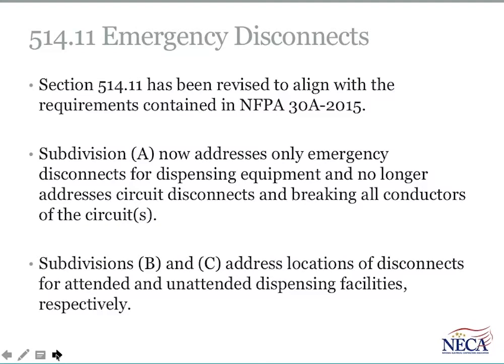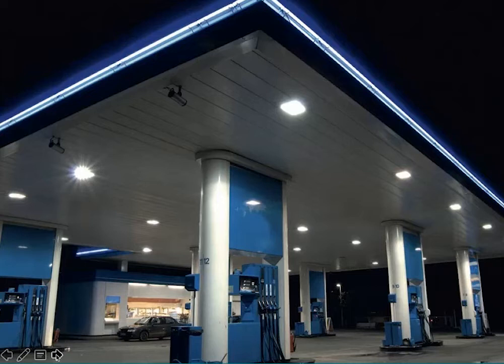That concept is handled effectively already in Section 514.13. So all you see that's left in here are rules that relate to locations and the requirements for emergency disconnecting means for attended stations and non-attended stations. The graphic just shows an example of a motor fuel dispensing facility, and the requirements are that there's an emergency disconnect switch that shuts all of them off or a group of them off, typically located for those users who are operating the fuel dispensing nozzles.